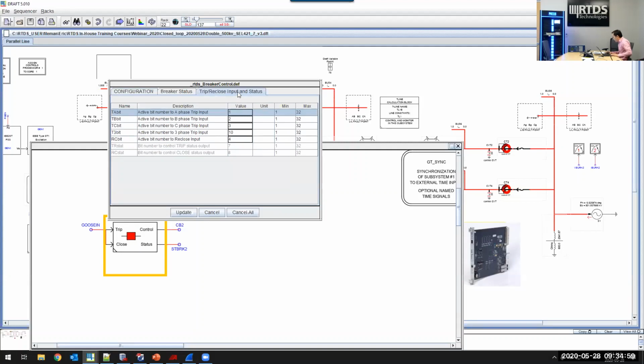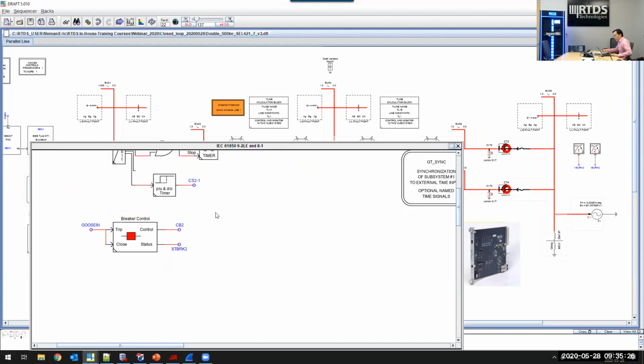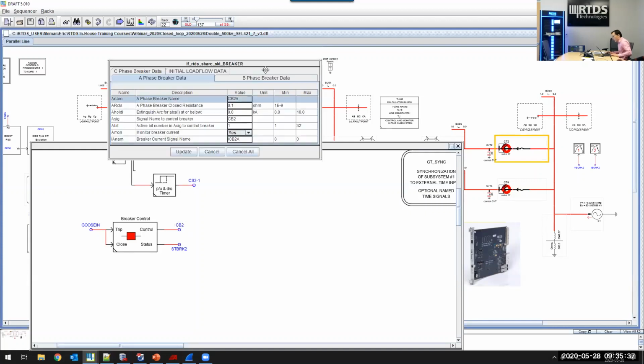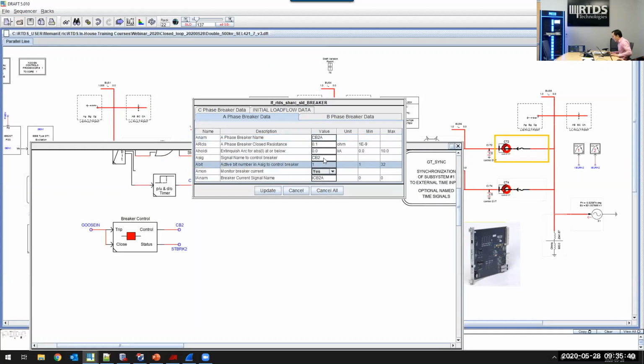As seen in this menu tab, bit 1 in variable GooseIn is now associated with A phase trip. Similarly down for B and C phase. And then bit 4 in GooseIn is used to reclose any opened phases. Now ignore this 3-phase trip input since it's not configured in the relay. The output variable CB2 here is then used as a control word to control breaker 2. Here we can see that bit 1 of CB2 controls A phase, and then bit 2 for B phase, and bit 3 for C phase.